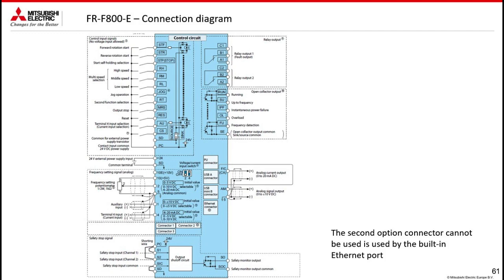Speaking of the analog signals, there is the 10E pin. This pin has been added and provides 10 volt, and there is also a further analog input, input 1, the pin 1, which is polarized. In fact, I can read plus or minus 10 volt, plus or minus 5 volt, and by default it works as compensation to increase or decrease the main value. If through input 2 I am driving at 50 Hz, I can slightly increase or decrease the frequency with input 1, therefore making micro calibrations in the order of a few hertz.